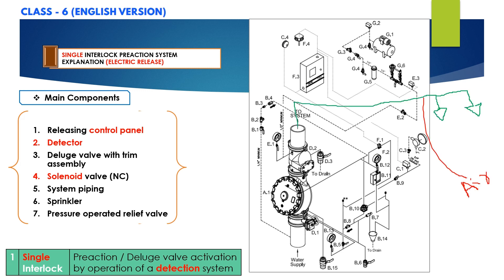Electric release systems utilize a deluge valve and a pneumatically pressurized automatic sprinkler system. Unlike dry type, the system piping here is pressurized only for supervisory purposes — this feature serves to prevent undetected leaks. If the system piping or sprinklers are damaged, supervisory pressure is reduced and a low air alarm is activated in the panel. Since the main purpose of a pre-action system is to not allow water to discharge in a no-fire condition, supervision ensures we know if there are any leaks or damaged pipes.